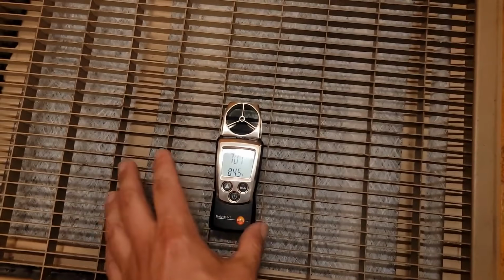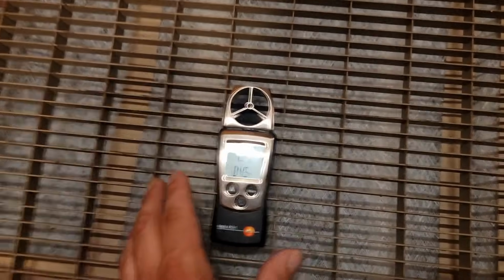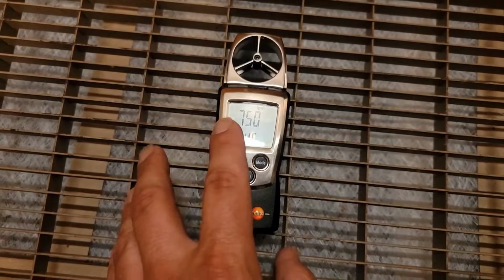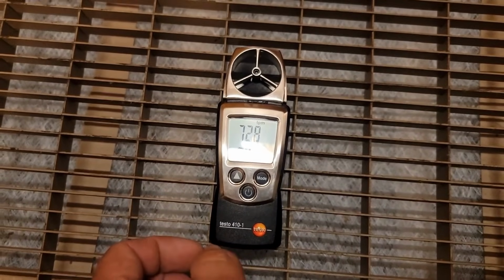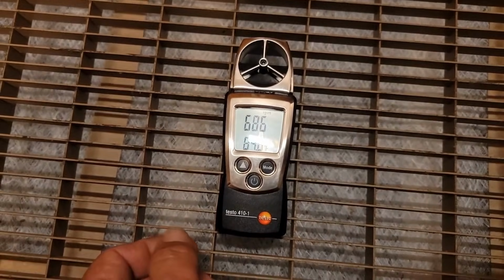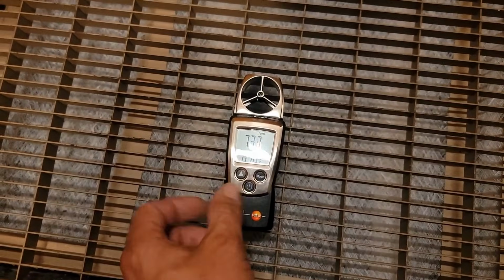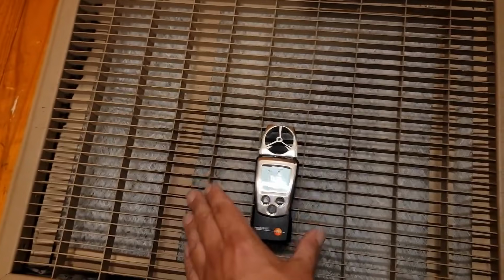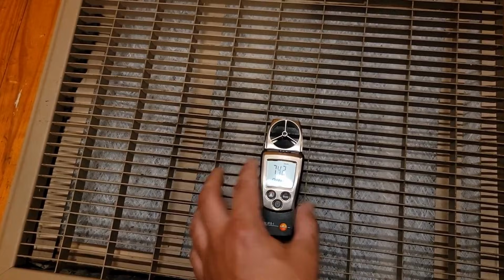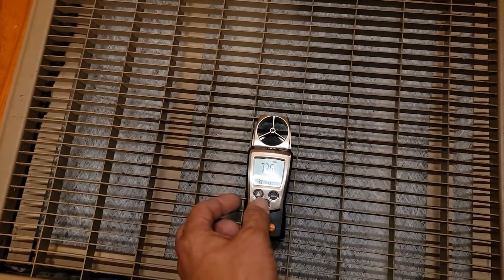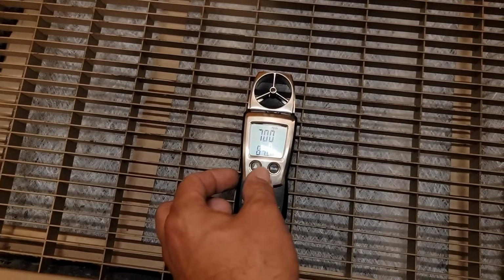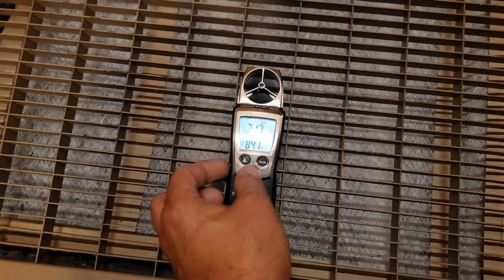And I'm going to leave my anemometer right here in this very spot so that after I adjust the fan speed, you can see what the feet per minute is. See, it's almost 750, or it just said 760. That's way too high. It should be no more than 500, and I may not be able to get it below 500, but at least I can get a better temperature split and get the airflow close to what it's supposed to be, okay? All right, I'll turn this off.